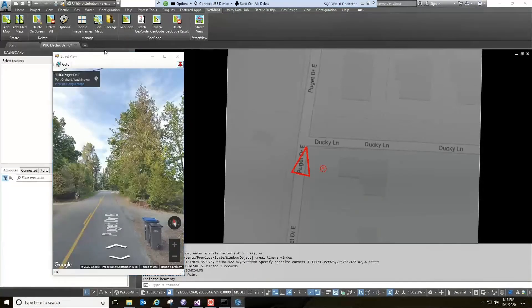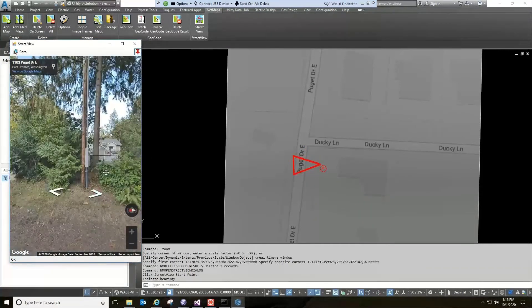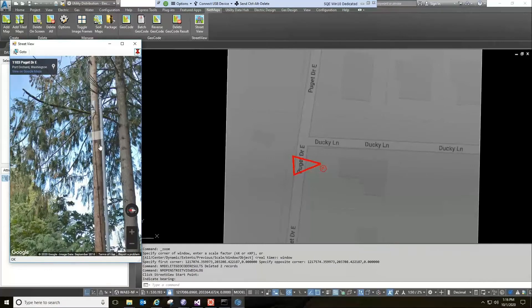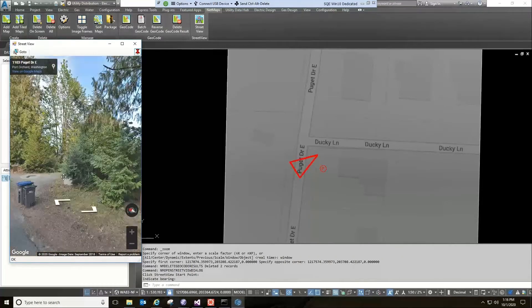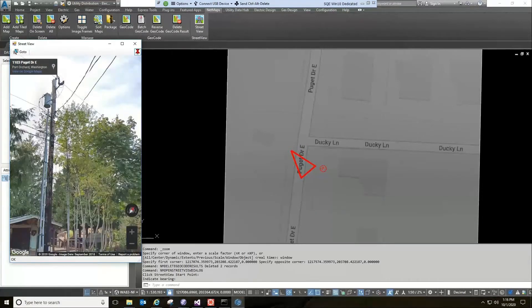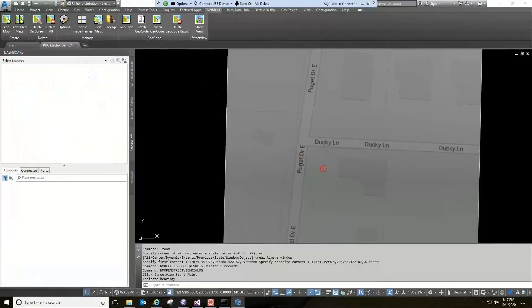I can lock the street view browser so it stays on top, then scroll around and find my pole that I just downloaded. I can see a picture of it — it has some kind of riser on it, a wire going across the road, and presumably another pole with a transformer and conductors. This is helpful to do a quick check and compare what I'll see when I import from the GIS.